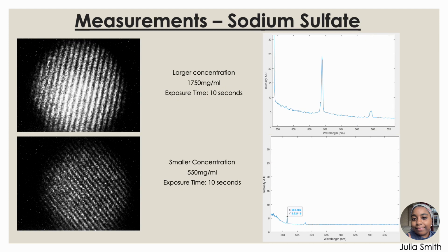So with this slide, it shows two different comparisons of sodium sulfate, but one has a larger concentration, one has a smaller concentration. And they both have an exposure time of 10 seconds. As you can see on the larger concentration, the fringes are brighter, they are more distinct, and with the corresponding spectra, the counts are higher, and you can more visibly see the doublet that we talked about in the last slide. Compared to the smaller concentration, the fringes are not as distinct, and the spectrum associated with it has a lower count, and some of the lines that should be distinctive to sodium sulfate are not distinctive because there is not enough Raman signal to detect those.